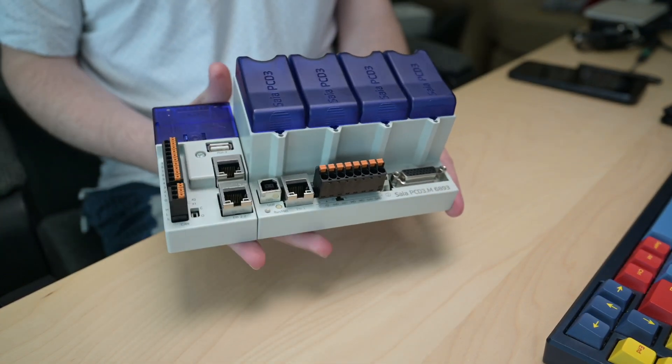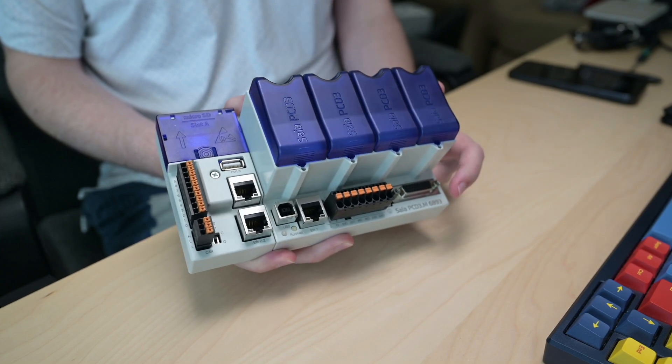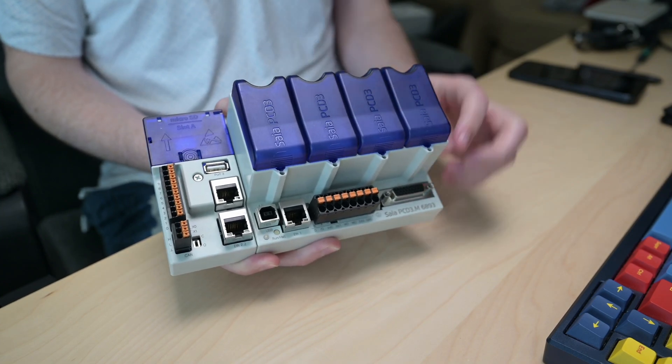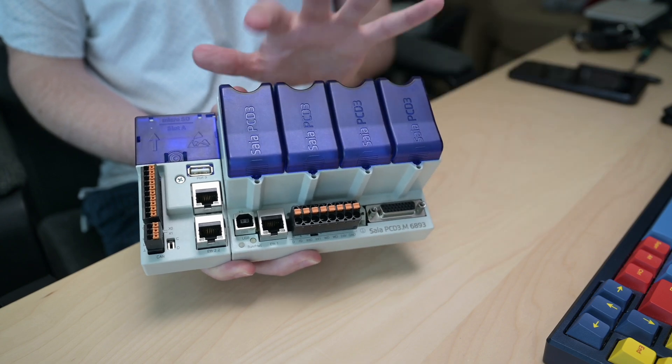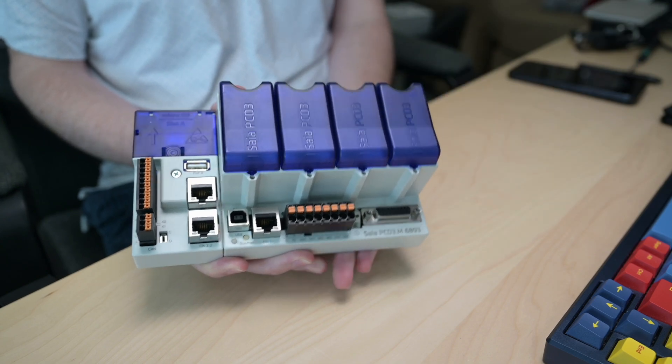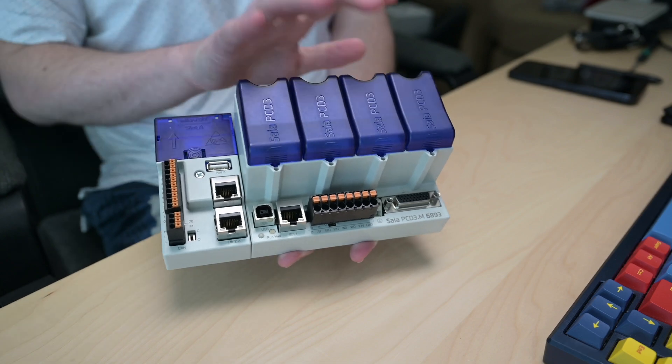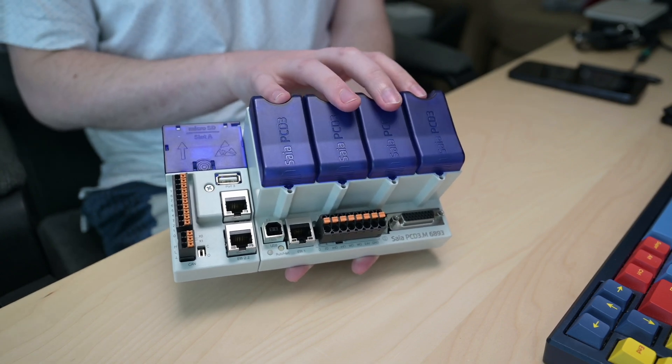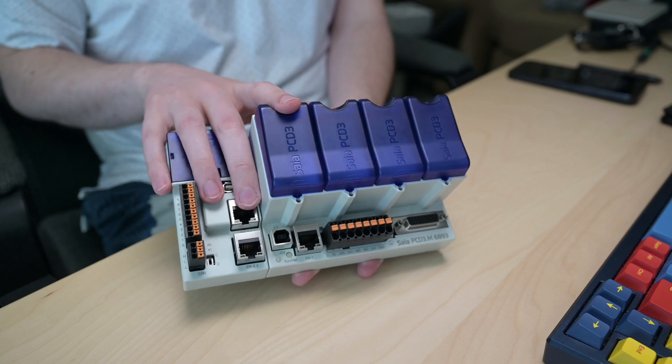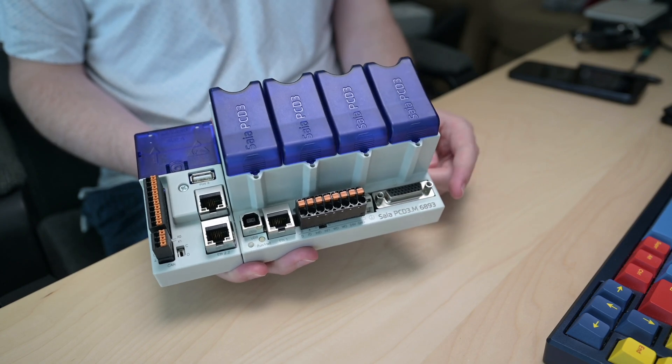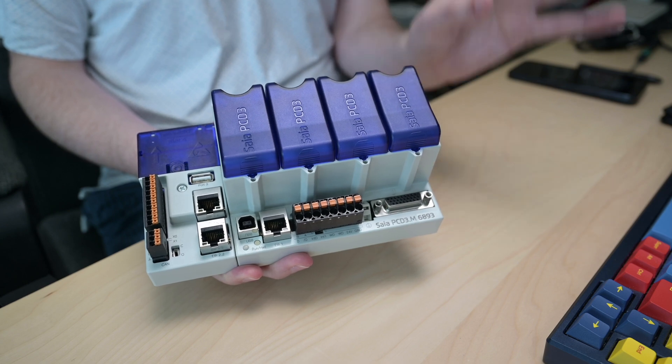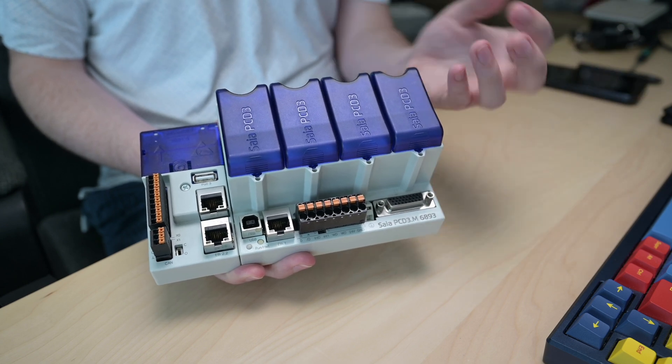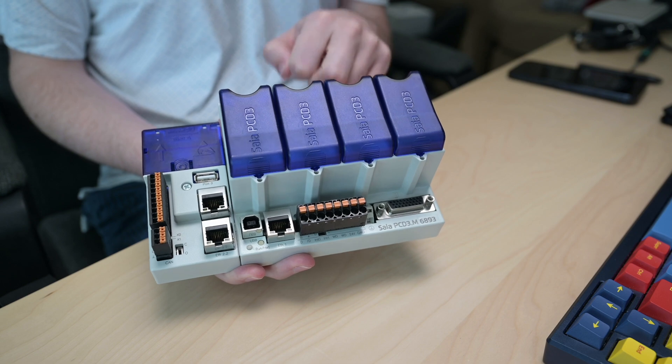Looking at the rest of the hardware, we've got a port down here at the bottom. This lets us take additional housings for our IO and strap them on the side of the controller itself. We can do quite a few of these. Something like up to a thousand points of IO could come back into this single controller, which is super handy. They also have the ability to use IP-based housings to bring the data back into the controller itself.